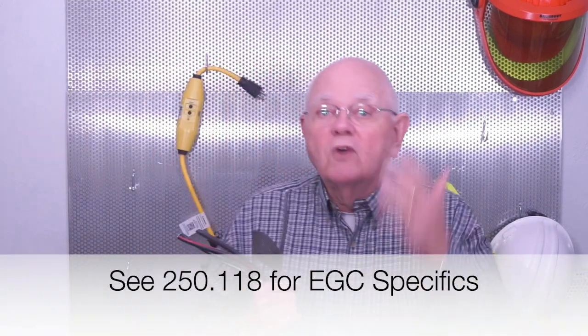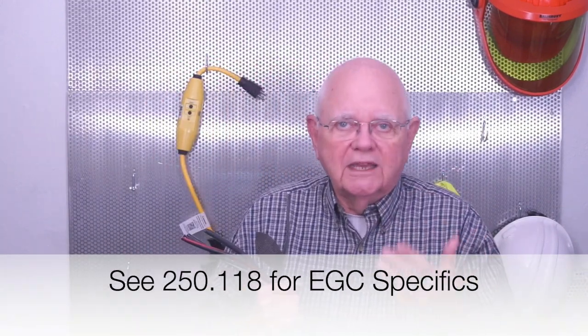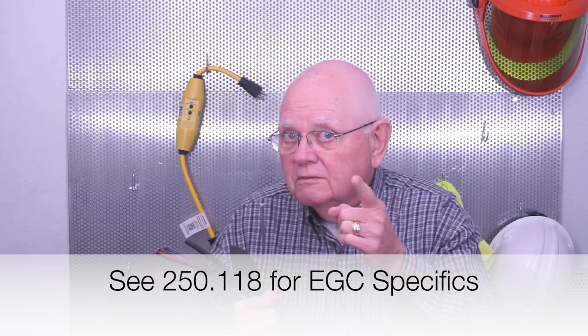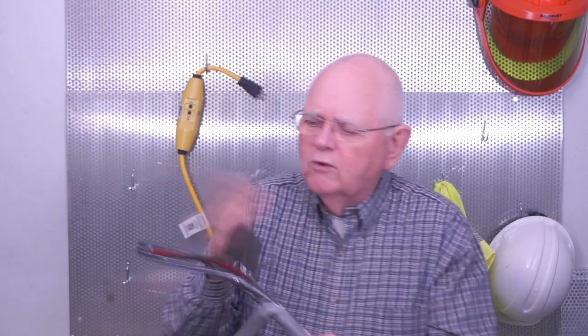250.118 tells me what I can use for my equipment grounding conductor, my EGC. And it says I can use either copper, aluminum, or copper clad aluminum. And of course, this is an aluminum conductor, so I can use that as my equipment grounding conductor. So anyway, commonly used, right? Type SE cable for branch circuits and feeders on construction job sites. No problem doing that. Just follow your requirements.